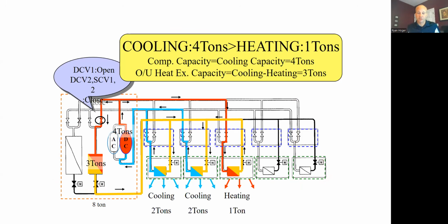If I was going to do VRF for a building, I would force it into this way. Force it meaning I would lay my building out so it looks like this. So in this case, I have my 8-ton unit. I'm asking for 4 tons of cooling, 1 ton of heating. By the way, a ton is 12,000 BTUs if you want to think of it that way. And then these 2 zones are off. No one needs anything, right? So normally I would run a 4-ton AC to take care of them. And I would run a heating, electric heat, gas heater, whatever, for 12,000 BTUs to take care of him.